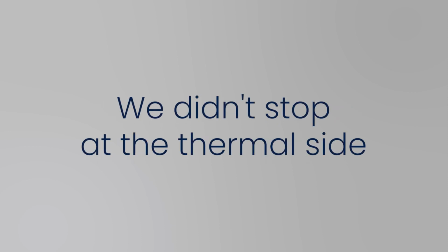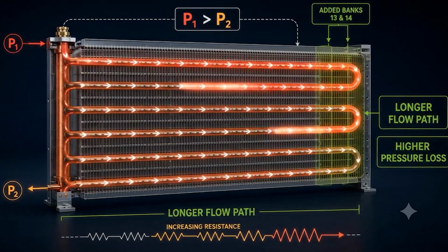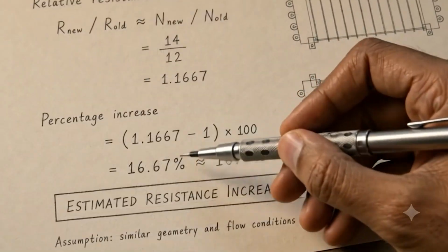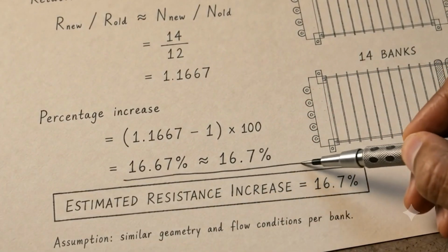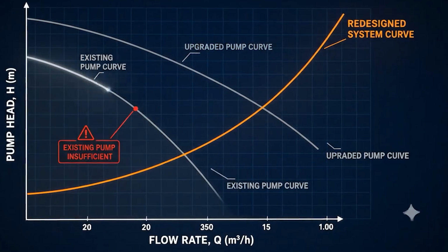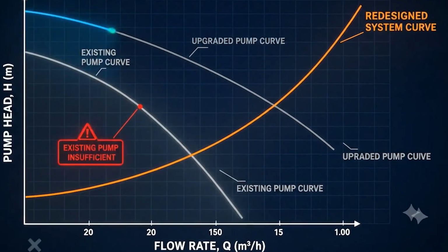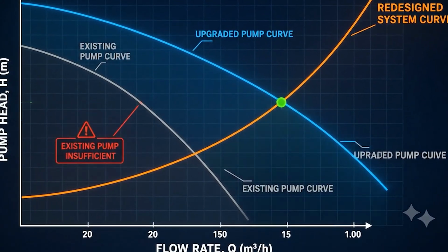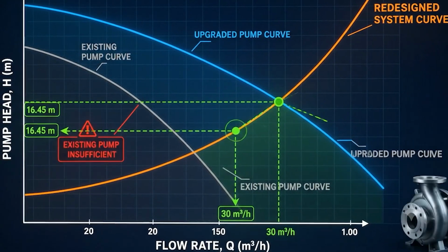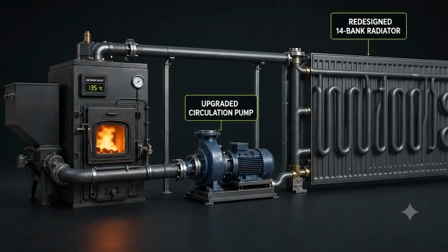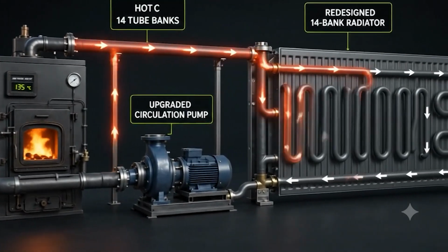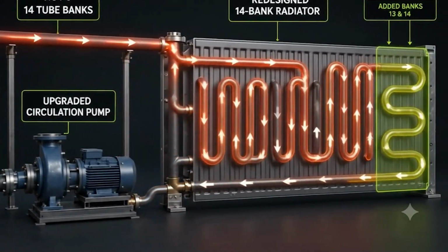We didn't stop at the thermal side. Adding more banks also increases resistance to water flow. We calculated this increase at approximately 16.7%. To maintain the required flow rate of 30 cubic meters per hour at 16.45 meters of head, the circulation pump needs to be upgraded. We identified this as a necessary supporting modification, ensuring the redesign works as a complete system, not just on paper.